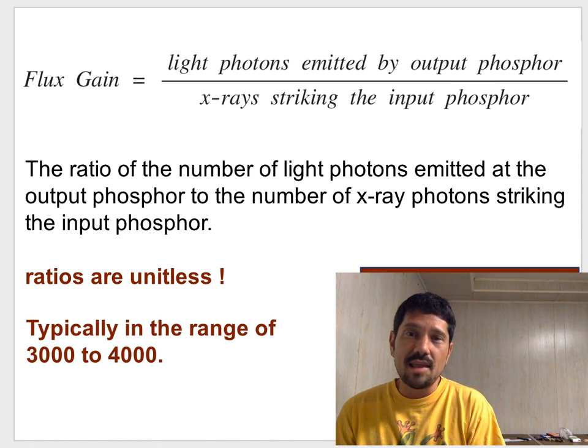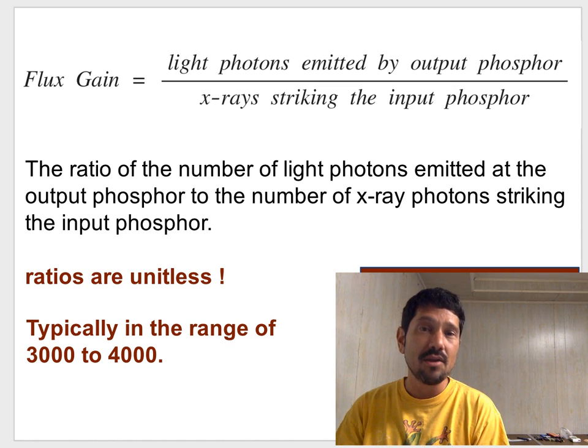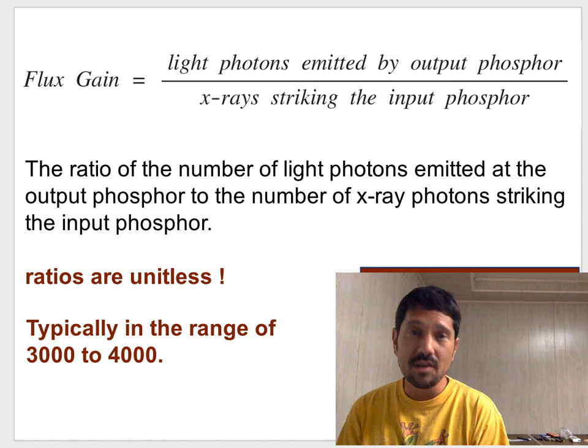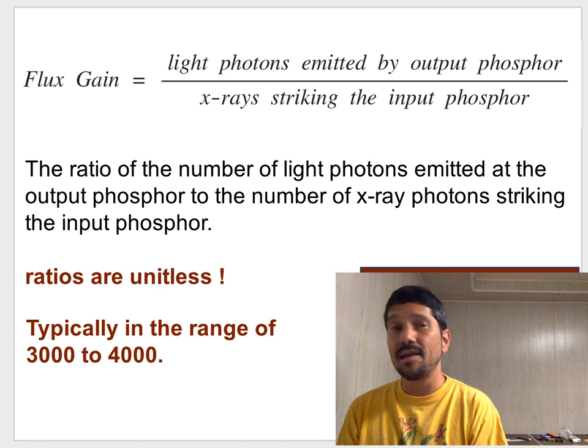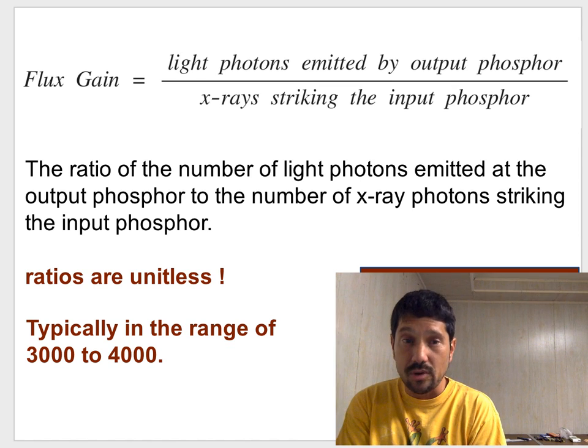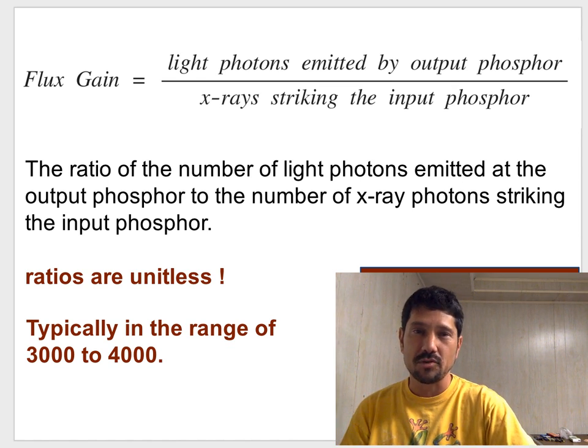The flux gain is looking at the ratio of the number of light photons coming out of the II relative to the number of X-rays that struck the input phosphor. So now we're doing what light comes out divided by what X-rays went in. Again it's a ratio so it'll be unitless. And flux gains are typically in the range of 3,000 to 4,000.